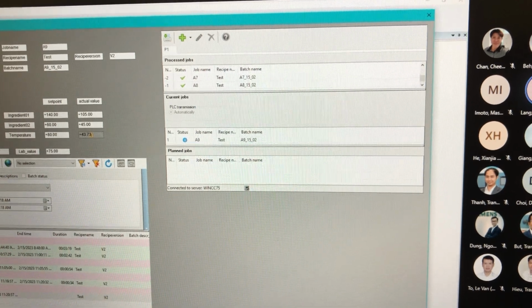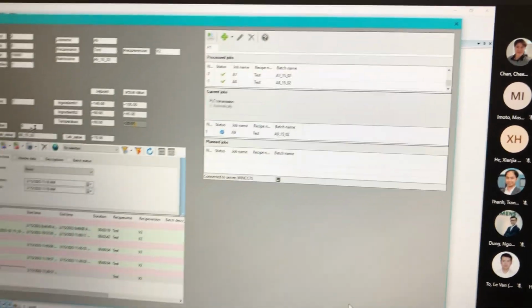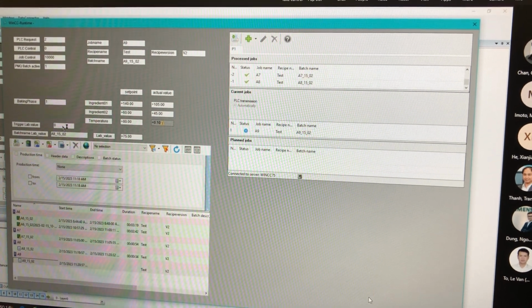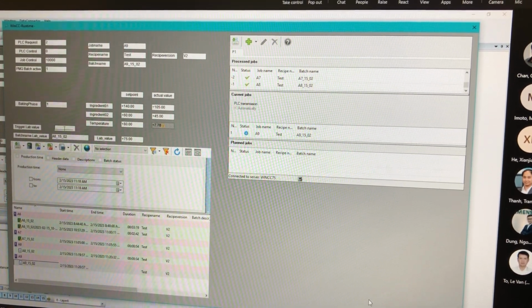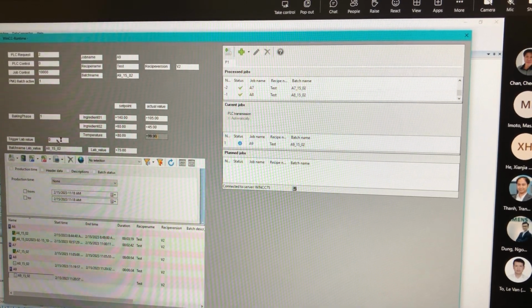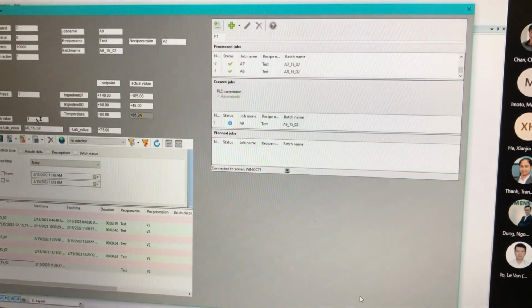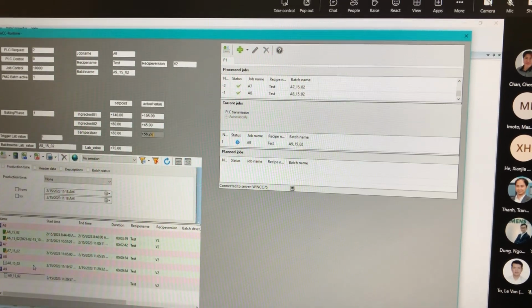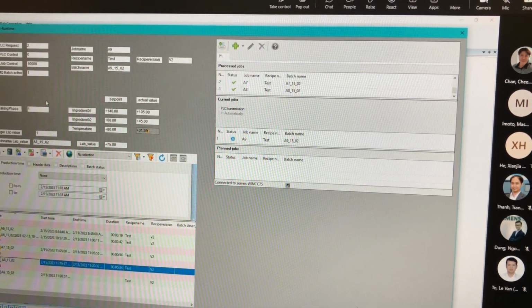And if I now change the trigger value, the trigger tag we have added to the snapshot group, then this snapshot should be recorded and should be saved inside of the batch we have mentioned here. So let's see if it's working. So if I change that one to 1, so now we should get the snapshot inside of this batch here.